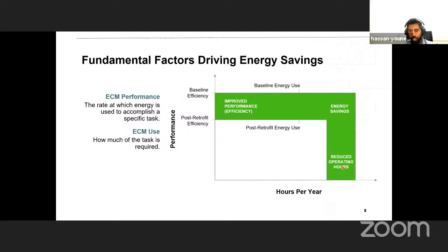So you have reduced operating hours. Let's say, for whatever reason, it's a school that's totally shut down in summer. You can theoretically turn off the chillers during summer. For whatever reason, the owner was keeping the chillers and the air conditioning system on when it's not needed. So you can reduce the consumption simply by turning off that chiller, reducing the energy consumption by reducing the operating hours.